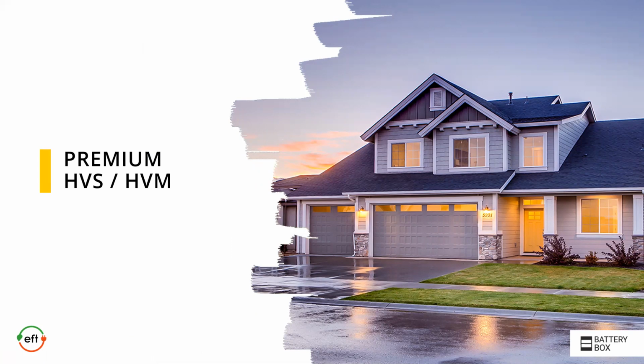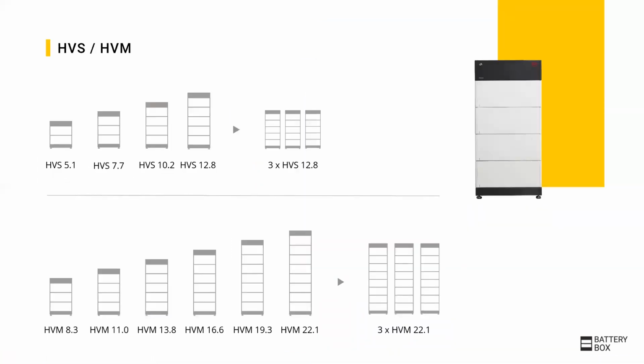After the general support information, we will now look into the product details and start with the premium HVS and HVM. First, a short product overview. The HVS consists of 2 to 5 modules per tower, which are connected in series, whereas each module has about 100 volt. The HVM consists of 3 up to 8 modules, also in series connection, whereas each module has about 50 volt. Up to 3 towers with the same module configuration can be put in parallel.